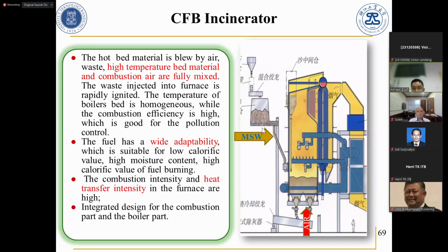This introduces the hot bed material being blown by air. The bed material is hot sand or reduced materials. Air is introduced from the bottom, so the high temperature bed material and combustion air are fully mixed, giving very good turbulence. The air mixes with MSW and coal, enabling combustion.